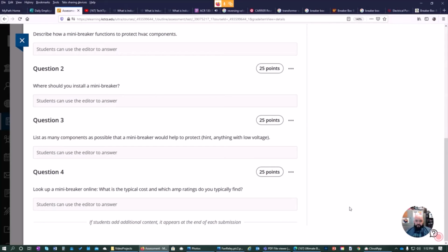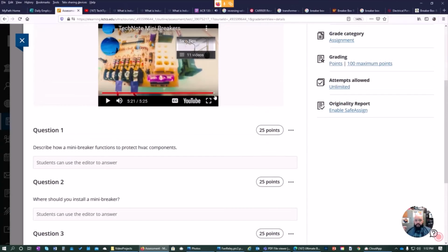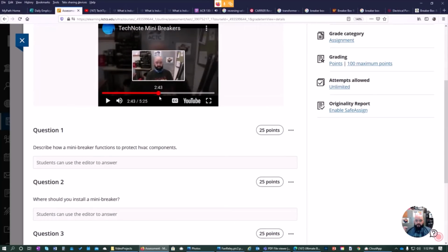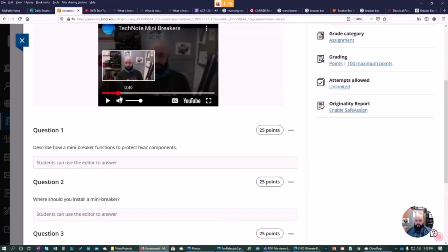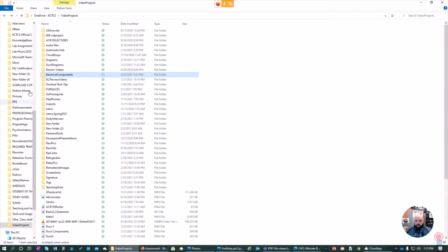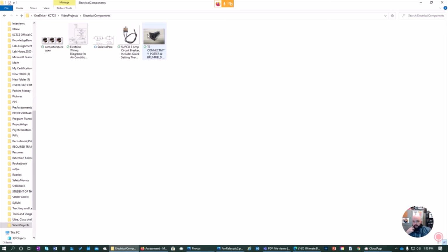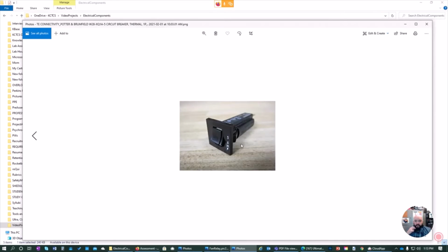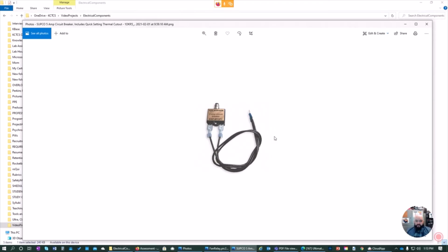Doesn't a mini breaker act as a safety? It is a safety. It is a fuse, essentially. The only difference between a mini breaker, let me pull one up here, show it to you. Oh, I know, better picture. The only difference between this mini breaker, the little popper, notice 3 amp breaker, is that they're resettable. They're not one time. Fuses, whether high voltage or low voltage, are one-time blow fuses. So once they trip, they're done.